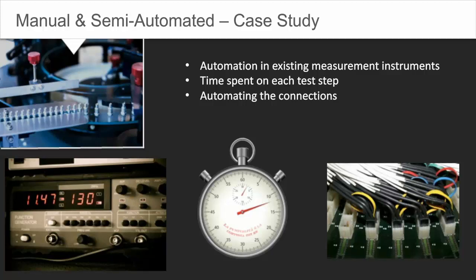And finally, we provided a test executive to them to run these test sequences and automatically print the test results and save them into a database for later searching. These enhancements reduced the total test time across several products by an average of almost 25%. Plus, the time to create the paperwork was reduced to about 2/3 of total effort due to the automated data collection. So how do you get started on enhancing your manual or semi-automated test system?